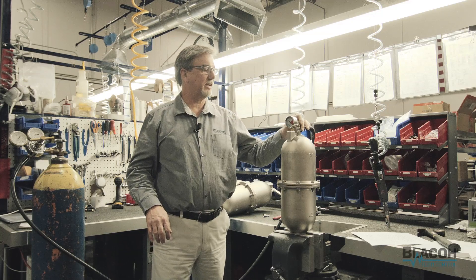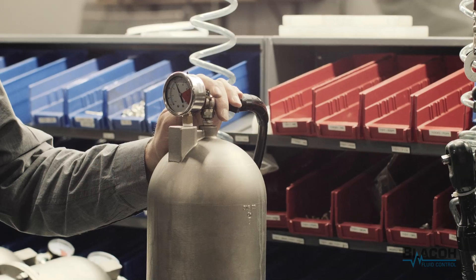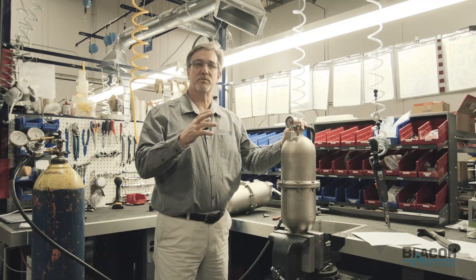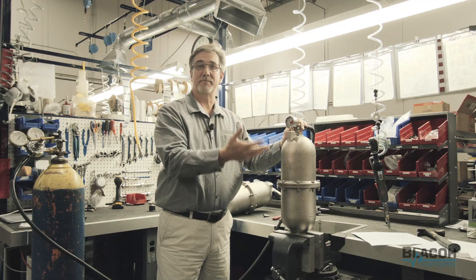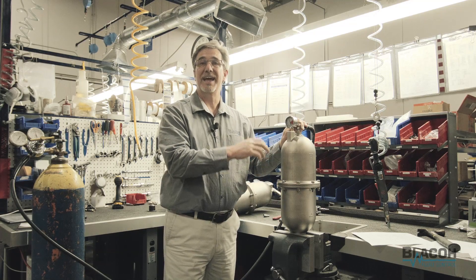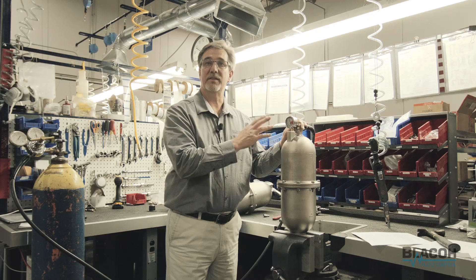We're allowing the charge to take place. After you have it, this is a standard tank valve, so it allows you to hit the core button inside to drop it down. Keep in mind that every time you run the system while you have it charged, the system pressure is going to be pushing up on that bladder. Whatever you see on this gauge lower than what you put in there, it will show up on the gauge. Also keep in mind that if you set it to 85 percent of your system pressure and then turn the system on, the pressure will increase, push the bladder up inside the unit, and you will then see the system pressure on this gauge. Ensure that you have a cap on the chargeable units after you finish charging them — that will keep the air pressure inside the unit.